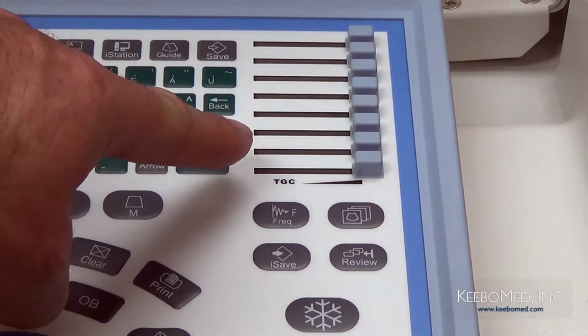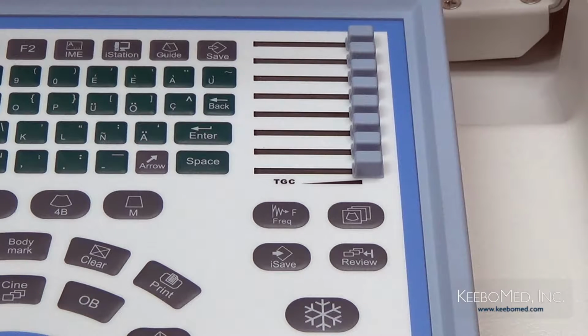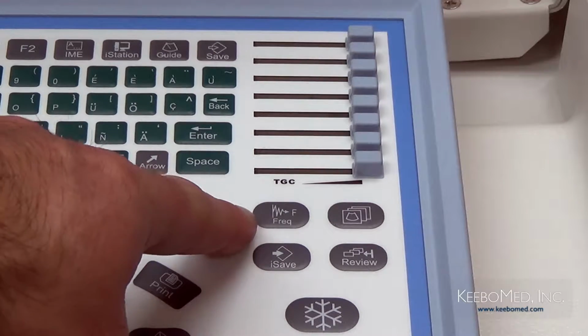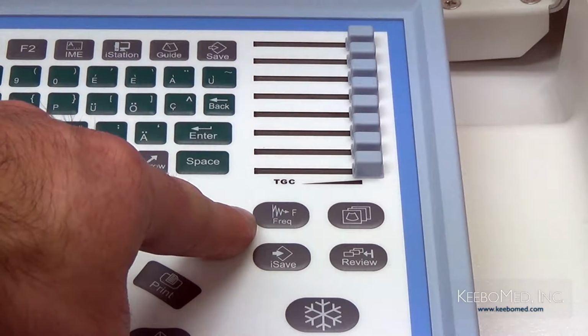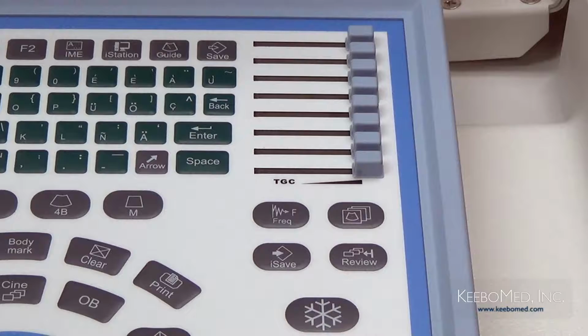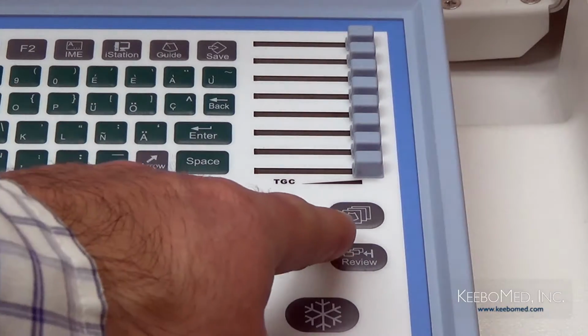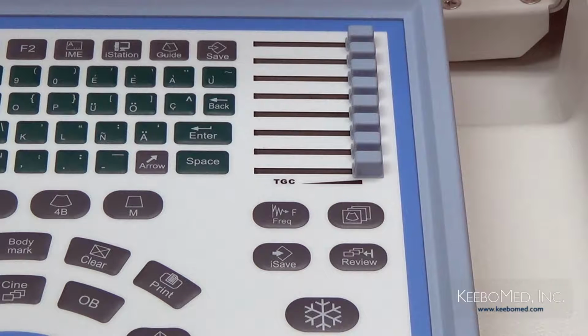At the top is the TGC control. There are 8 different segments to adjust the gain at different depths. Below the TGC control is the frequency key. Pressing this key will change the probe frequency quickly. Next is a shortcut key to adjust the frame average. Pressing this in real time will adjust the frame average in 4 different levels.